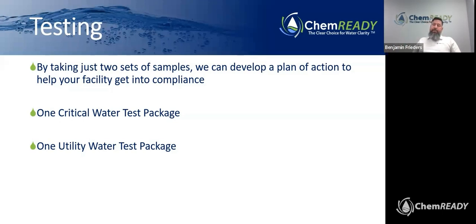So what does that do? That gives you time to budget it into your fiscal year, right? That gives you time to find vendors that can help you do the installation if you require equipment. What these tests also do is, best case scenario, you've done some legwork up until this point and you take a critical water test and you meet all the parameters at critical water, you're in better shape than most because your system's already putting out the quality of water, which is the whole point of the standard.